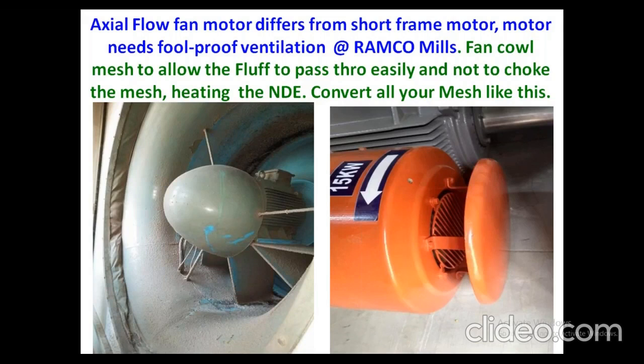In any textile mill, this is a Siemens motor, and this type of fan cowl has to be fixed for all the motors in the textile mill. It need not be there in other industries, but in a textile mill the textile fluff has to go through this fan cowl mesh and come out. If it is not able to come out, the motor driven-end and non-driven-end temperature difference should be less than 10 degrees, but it goes to more than 30-40 degrees also. So this is mandatory for all the motors, but not for the axial flow motor, because it is already cooled by the supply air fan that is being sucked. So it doesn't need this as such.